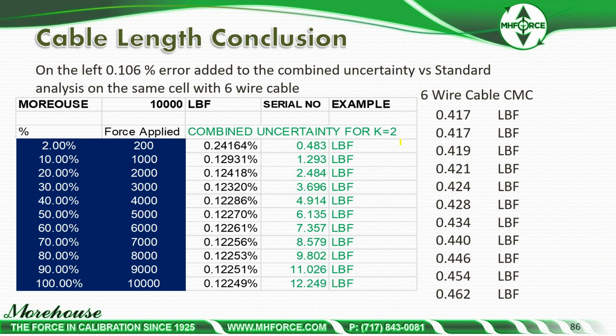The error in class, we used a 4-wire cable, same gauge, 6 feet versus 10 feet. And it produced a 0.106% error. I think that was 22 gauge cable, if I'm not mistaken. That is important to know, and I don't know that off the top of my head, but it was somewhere in that ballpark, 22, 24 gauge. And just the additional 4 feet produced an error of 0.1.